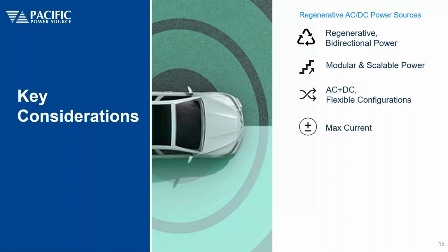Another important consideration is what is the maximum current that you need, and in particular, at what voltage. If you deal with a product that has a variable voltage range capability that operates over a wide range, it will typically draw more current at low voltage than it will at high voltage. So having a range of current capabilities as a function of the program voltage can be an important consideration, not just the maximum available current of the grid simulator. So it's something to also take into consideration.